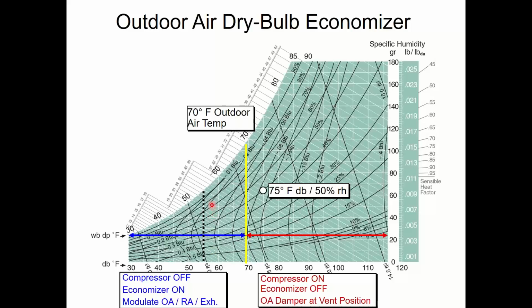But look what happens over here. If I had a 90% humid day when it was 55, that's 60 grains of moisture. But if I had a 90% humid day when it was 68, that's 100 grains of moisture. It's almost double the amount of real moisture. Well, why does that matter, Ryan? It's only 90% humidity. Yeah, 90% humidity at those temperatures. When it comes into the building, it's all going to be the same temperature as my indoor temperature. And now I've got almost double the amount of moisture, which is going to cause humidity complaints in the building.